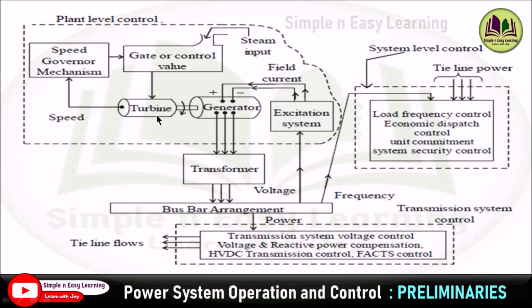The speed governor control deals with speed regulation. The turbine speed is sensed by a sensor and this speed is compared with the reference speed; the differential speed is sensed by the speed governor. The main operation of the speed governor is to control the speed corresponding to the differential speed by closing and opening the control valve. If the differential speed is low, the control valve is opened so that steam can flow at higher speed, thereby increasing the speed of the turbine.